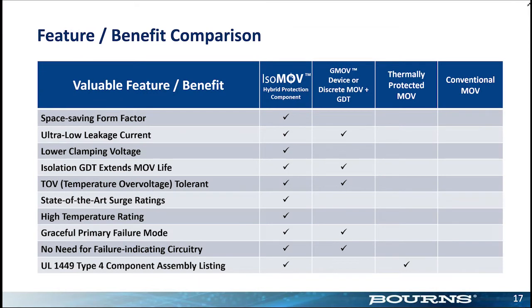Let's look at some of the benefits. There's a bunch of check boxes here. Are they small? Low leakage. I talked about a lot of these, lower clamping voltage. Does it have the GDT to extend the life? Overvoltage tolerance, et cetera, et cetera. And MOV, it doesn't really check any of the boxes. It's like I said before, it's better than nothing. It's kind of your first gateway into a protection product. The thermally protected MOV is UL certified, but it's still an MOV, so it still has some of these other issues. The GDT does not extend its life. It does not have state-of-the-art surge ratings.